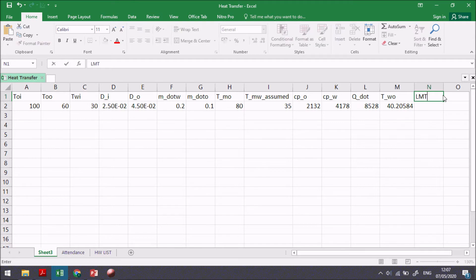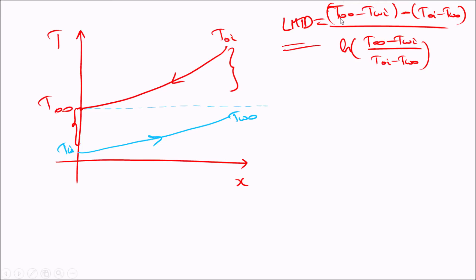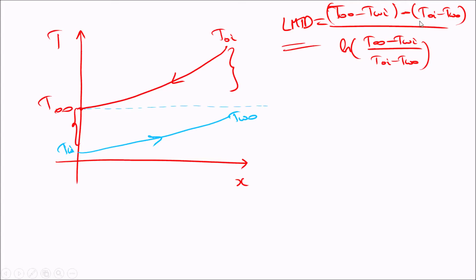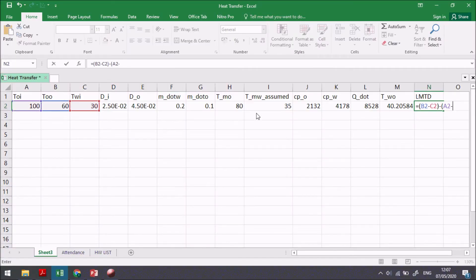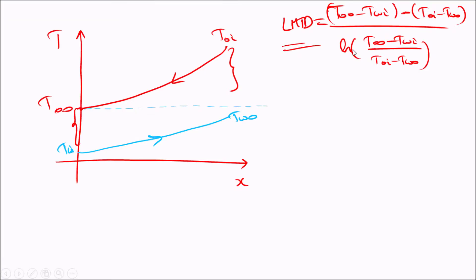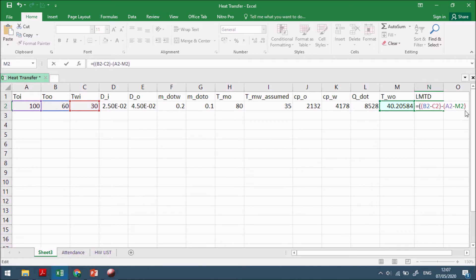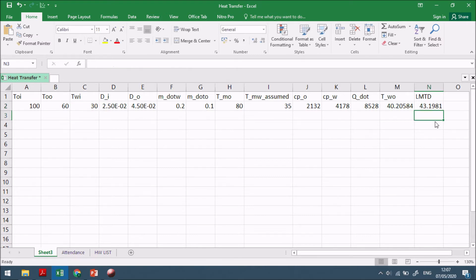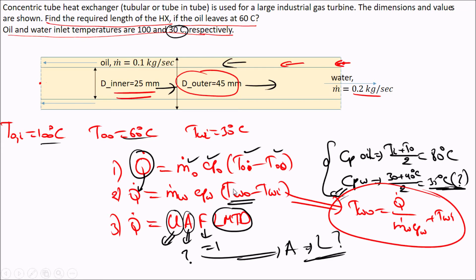In Excel, LMTD is computed as: numerator = (T_oil_outlet − T_water_inlet) minus (T_oil_inlet − T_water_outlet), denominator = ln of the same quantity. The result gives LMTD = 43°C. F equals one for the counter-flow exchanger.